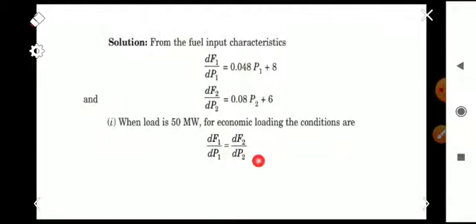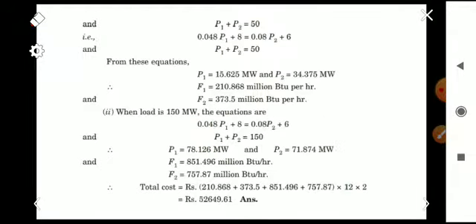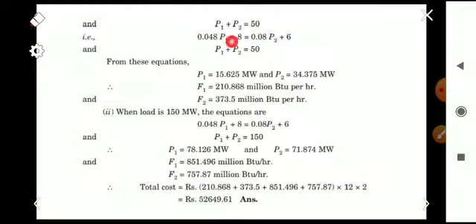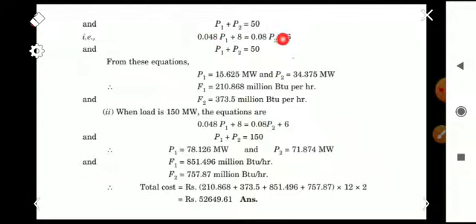When the load is 50 megawatt, the economic loading can be found by equating the incremental cost of production: dF1/dP1 = dF2/dP2. Also, the total load gives us P1 + P2 = 50. We have two equations. Substituting the values and solving these two equations, we get P1 = 15.625 megawatt and P2 = 34.375 megawatt.